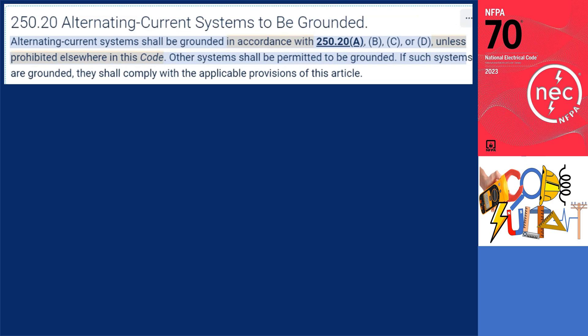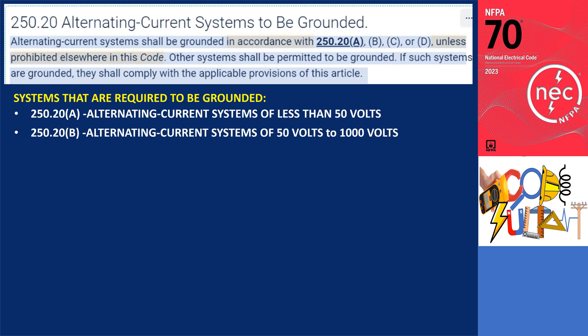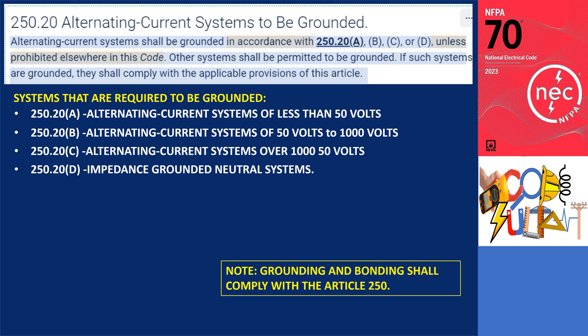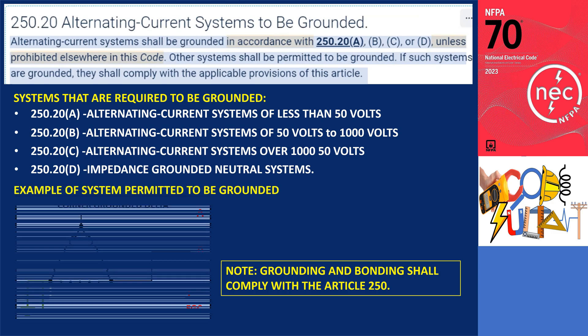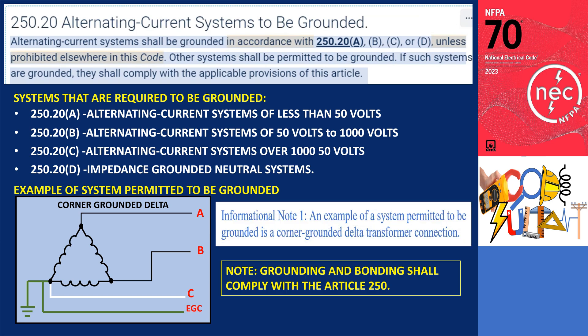Other systems shall be permitted to be grounded. If such systems are grounded, they shall comply with the applicable provisions of this article. Systems required to be grounded are stated in sections 250.20 A, B, C, or D. However, if a system is grounded even though the code does not require it, it shall comply with the grounding rules under this article. An example of an AC system permitted but not explicitly required to be grounded is a corner delta transformer connection, as noted in informational note one of the same section.